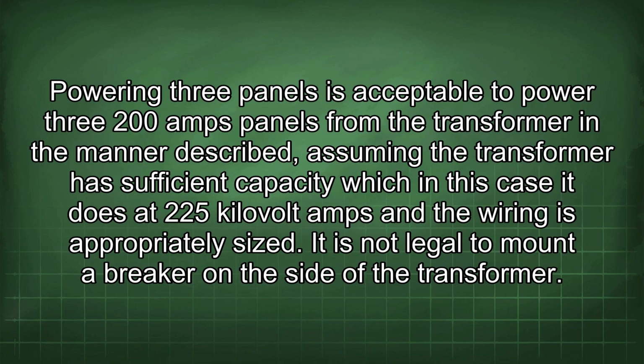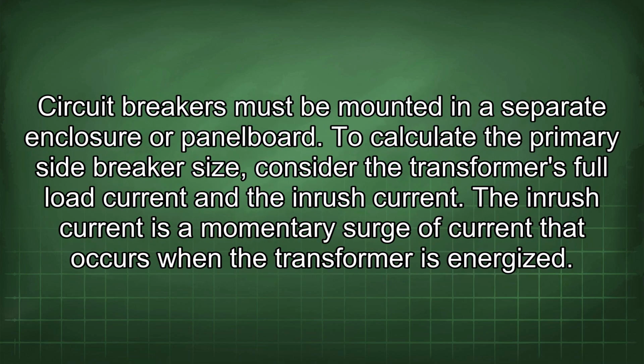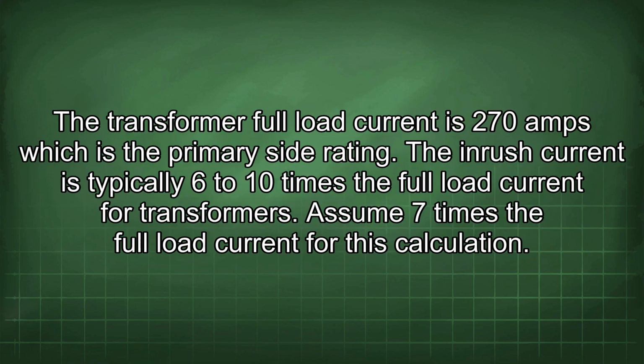It is not legal to mount a breaker on the side of the transformer. Circuit breakers must be mounted in a separate enclosure or panel board. To calculate the primary side breaker size, consider the transformer's full load current and the inrush current. The inrush current is a momentary surge of current that occurs when the transformer is energized. The transformer full load current is 270 amps, which is the primary side rating.